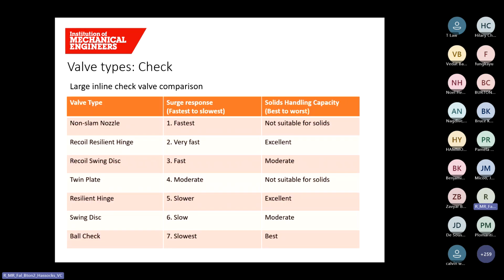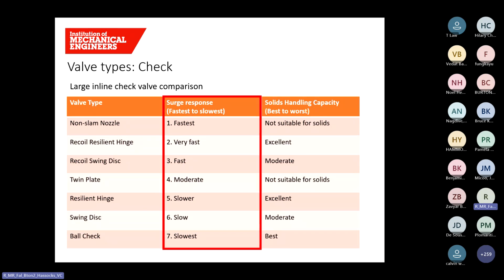Let's evaluate large inline check valves. The two key factors that stand out are surge response and solids handling capacity. Speed matters when preventing backflow and water hammer. The nozzle type leads the different types of check valve with the fastest response. This is followed by the recoil resilient hinge and recoil swing disc designs.